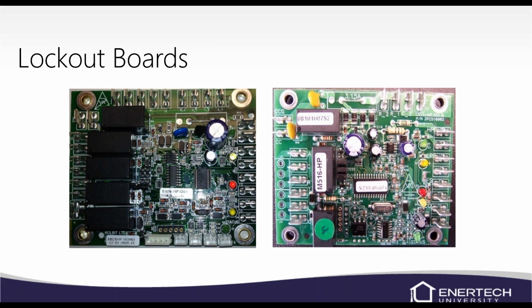There are some test jumpers on both boards. You can see them a little bit better on the one on the right, where you've got that relay that says M516-HP. Right to the right of that, there's a couple little black rectangles, and you can kind of see next to them, one says test, one says O/V, and the top one says WSD. Those are jumpers you can remove and get it to operate a certain way.